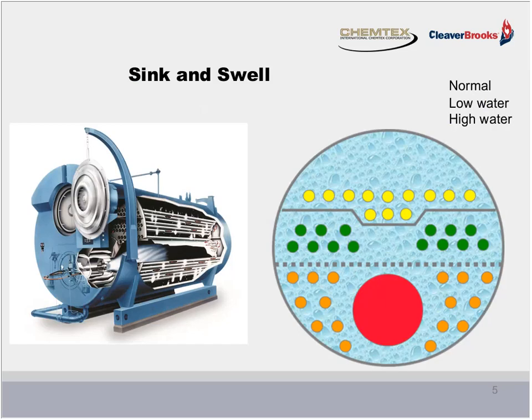Now, we'll start with sink and swell, and its primary cause, which is a change in ratio between the water mass and the vapor content. The vapor content being the steam bubbles forming as the water begins to change state. And as this happens, the water volume in the boiler begins to rise only slightly above the normal level, as depicted by this blue line. And then as the steam forms and exits the nozzle at the top of the boiler shell or the drum, the volume drops and triggers the pump control switch in the low water cutoff to close and start the boiler feed pump. This happens, of course, before a low water condition occurs, which would, as you know, break power to the burner and shut the boiler down.